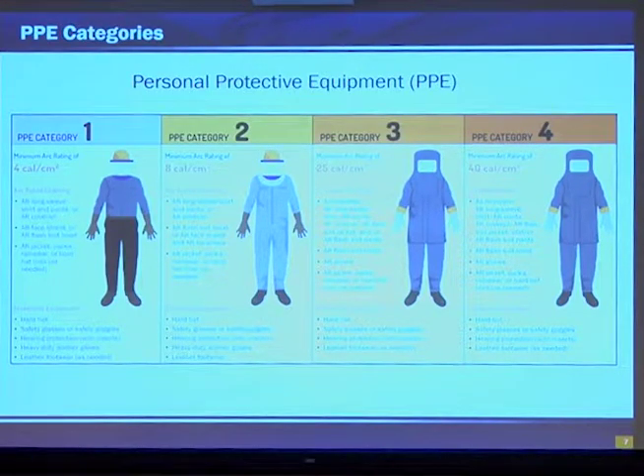Sorry. So looking at PPE Category 4. PPE Category 4 actually begins at 25 calories per centimeter squared to 40 calories per centimeter squared. Category 3 begins at 8 calories per centimeter squared to 25 calories per centimeter squared.